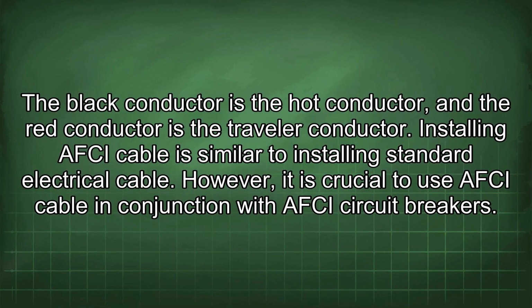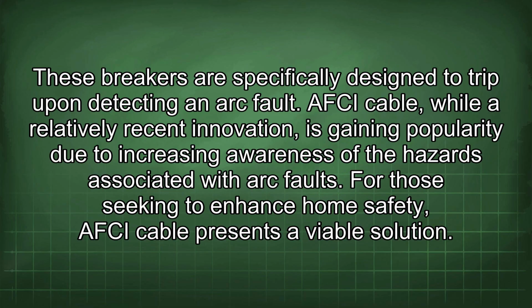Installing AFCI cable is similar to installing standard electrical cable. However, it is crucial to use AFCI cable in conjunction with AFCI circuit breakers. These breakers are specifically designed to trip upon detecting an arc fault. AFCI cable, while a relatively recent innovation, is gaining popularity due to increasing awareness of the hazards associated with arc faults. For those seeking to enhance home safety, AFCI cable presents a viable solution.